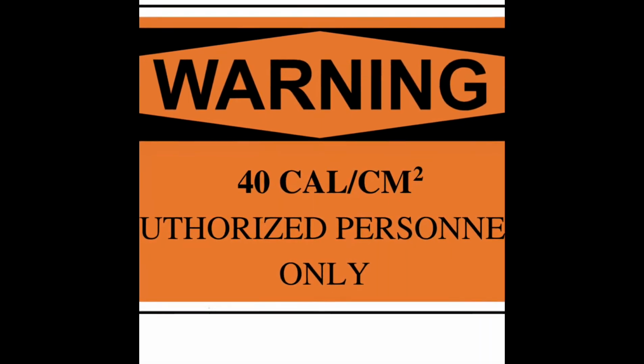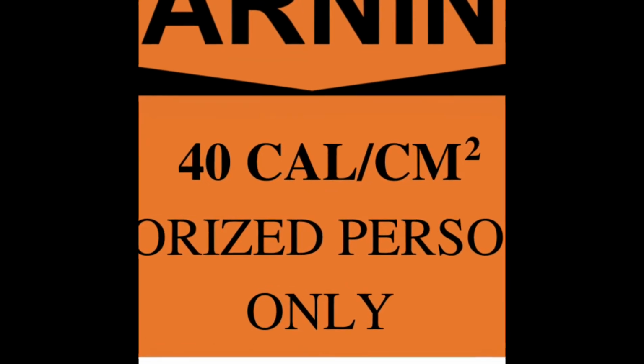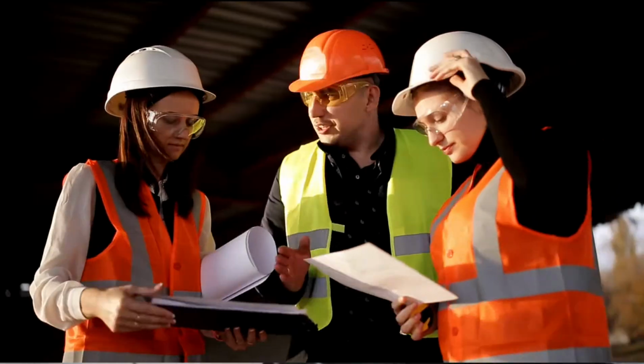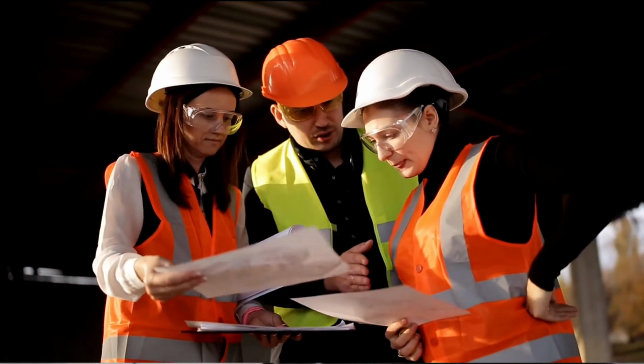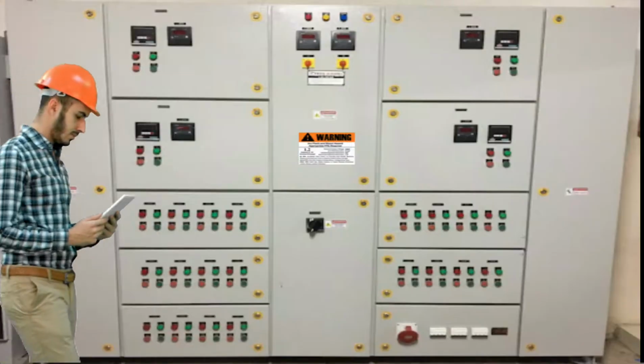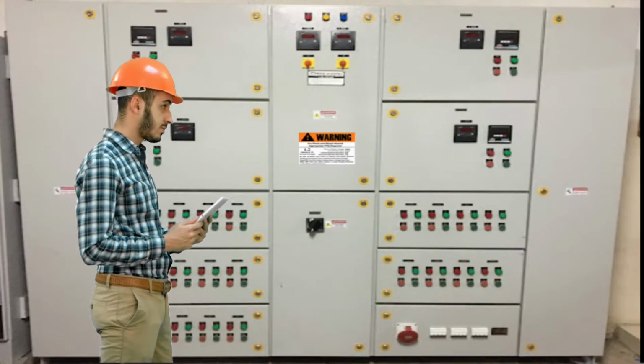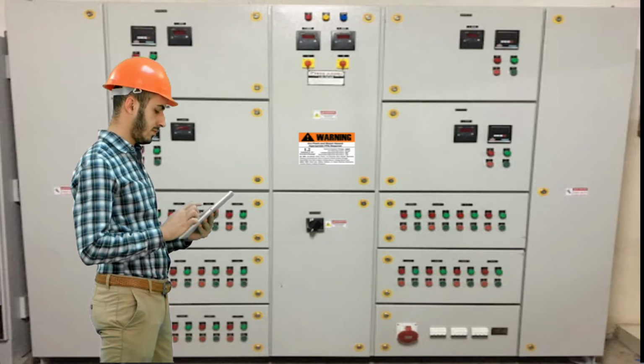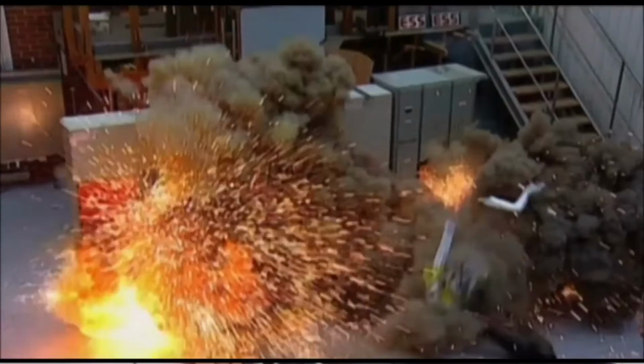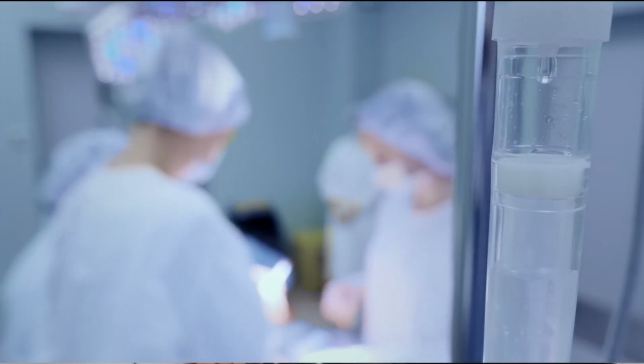In the US, the thermal severity of the arc flash hazard is measured in calories per centimeter squared. This is the amount of heat that is generated in a specific area. There are multiple hazards associated with an arc flash. Regarding the thermal hazard, any thermal hazard greater than 1.2 calories per centimeter squared is considered a significant hazard that could result in a second-degree burn or worse to any person sustaining the hazard. When an arc flash occurs, the flash is immediate, but the results can cause severe injury. Over 2,000 times a year, workers are admitted to burn centers for extended injury treatment caused by arc flash.